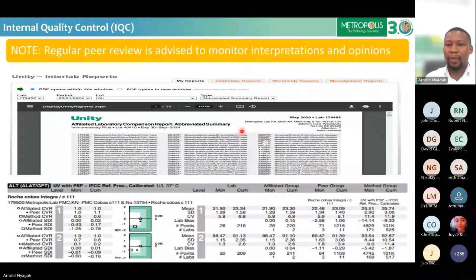So the other requirement on IQC is that the IQC material shall have 4 things, okay? One of them is that it has to be stable with regard to properties of interest, okay? And so for the stability, you can get this from the kit insert, how stable the material that you are procuring is. Then it has to have a matrix as close as possible to patient sample, okay? So I believe my colleague has talked about the matrix bit in detail. Then it has to react to the examination method in a manner as close as possible to patient sample, okay?